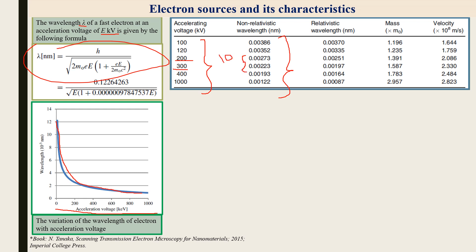Most advanced TEM systems operate at 300 kV or 200 kV. At these voltages the wavelength is in the 10⁻¹² meter range. With this wavelength, the radiation is able to view atomic-scale features. We need to break the wavelength limitation of optical microscopes using the acceleration voltage and wavelength relationship to achieve atomic resolution.